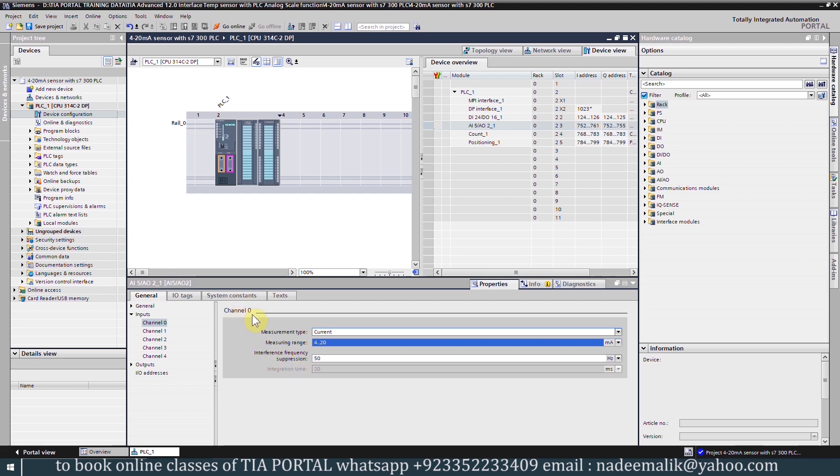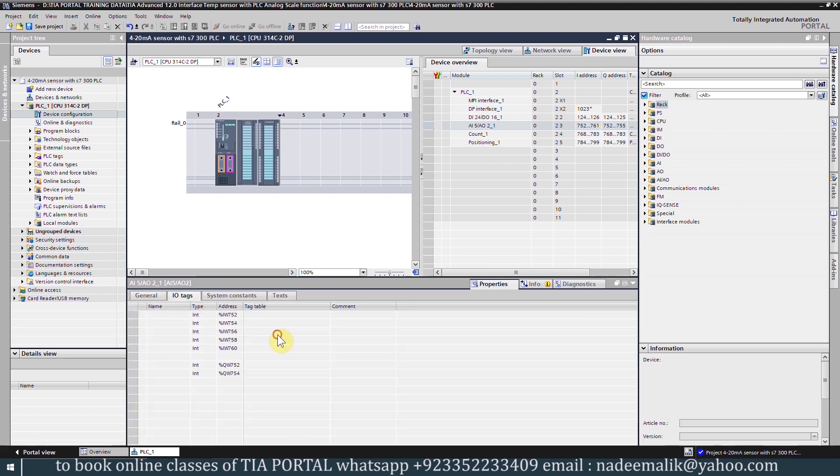Next we will go to the IO Tags tab. Here you can see the addresses of the analog input channels. The address for channel 0 is IW752. The analog values from the transmitter connected at channel 0 will come in this input word 752.